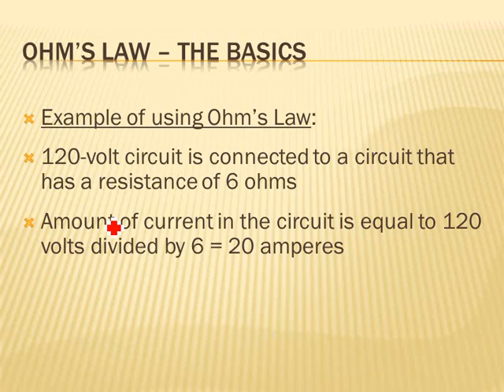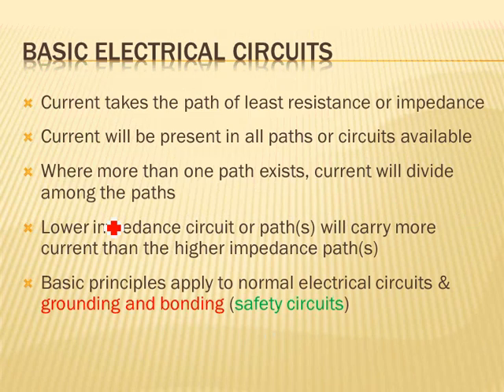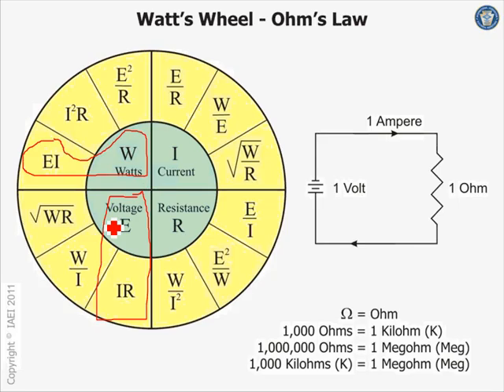Okay, this is just a couple of examples, guys, of how to use Ohm's law and so forth. I want to emphasize the basic principle applies to the normal electrical circuits and the grounding and bonding circuit. We're interested in Ohm's law, the whole circuit that you did. The higher the impedance, the less current that you can push through it. That applies to the normal operation of a fixture, a light, as well as the abnormal operation of equipment. What's the abnormal operation of equipment? You have a ground fault right here. All the current is going to bypass, cut through here, and go right through that short circuit of the ground fault all the way to the source. So if that conductor is not sized enough, it's not going to allow the current to go fast enough, large enough through it to facilitate the operation of the overcurrent device. So Ohm's law, guys, applies to normal operation of equipment as well as abnormal operation, which is short circuit and ground fault. So just keep this in mind.